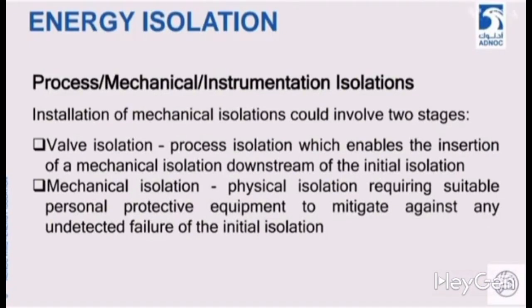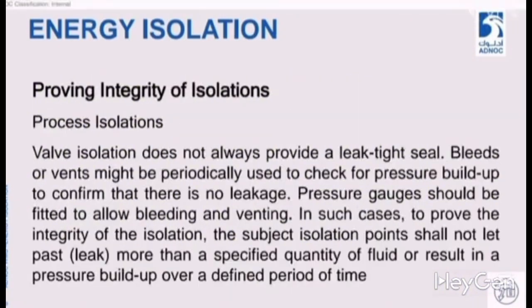Next, we have mechanical isolation, physical isolation, which requires suitable personal protective equipment to mitigate against undetected failure of the initial isolation. We controlled the valve and isolated it, and then we also placed a blind ahead of it so that if our valve fails or if our process isolation can leak or fail, our blind, which was our dead end, will ensure that no source of energy or supply can come and expose our people to harm. During work, our people remain safe from this type of energy source.